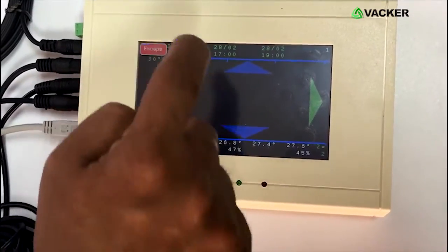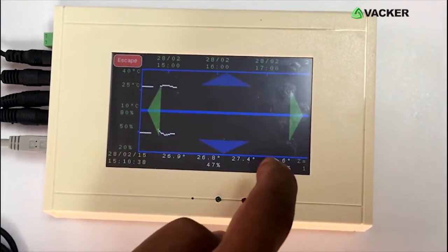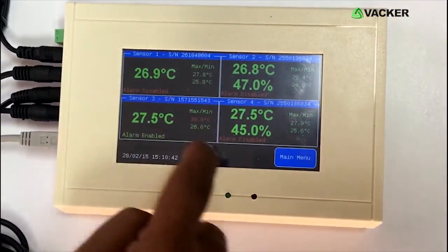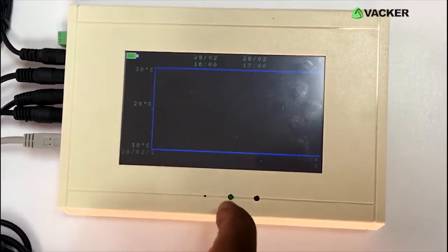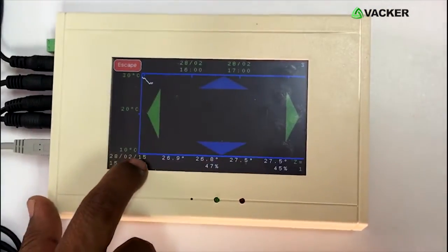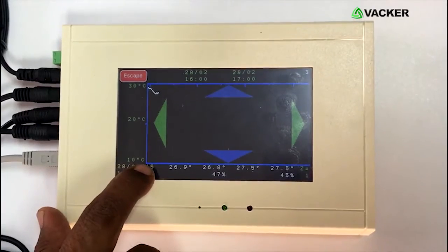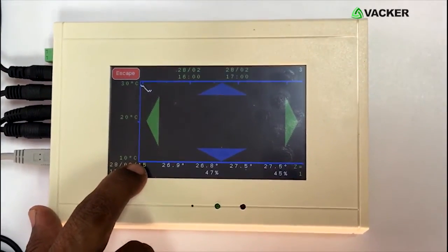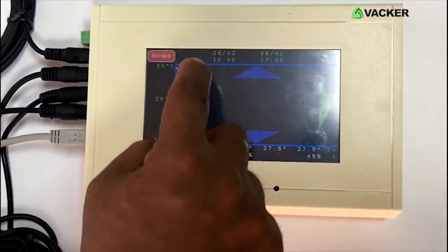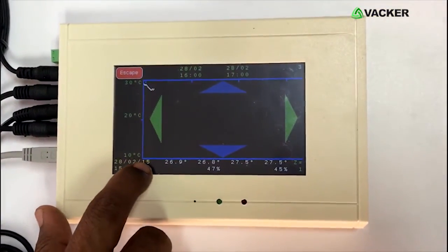To go back, press escape. This is the humidity and temperature sensor. You can see both the graphs here, and similarly you can see for all of them. You can see that the upper and lower limits were programmed from 10 to 30 degrees Celsius. That is why it's showing 10 to 30, but this does not have any effect on recording.